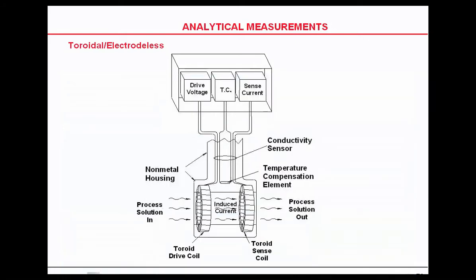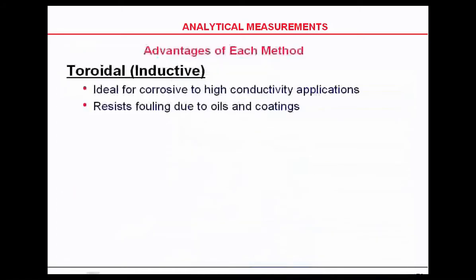So you're basically sending conductivity from the left side to the right side, measuring the conductivity, and going back to your analyzer again. It's ideal for corrosive and high conductivity applications. It's also very good in dirty and fouling applications that would foul up a contacting conductivity.